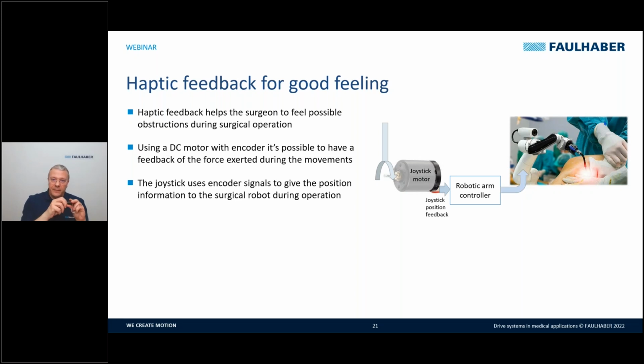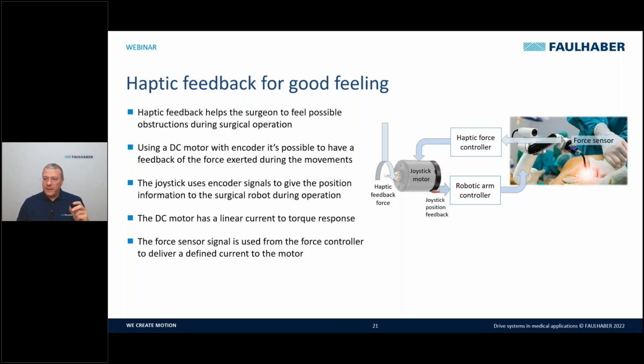that we can give. This is for one axis, and a manipulator can have more axes, for example, for complex movements. On the other side, you know that this kind of DC motor has a linear current to torque response, so it's quite easy to generate a torque proportional to the motor current. And this is possible from a haptic force controller. It gets the information of the force sensor, and based on this, it can generate a current to the motor, and the motor generates a torque.